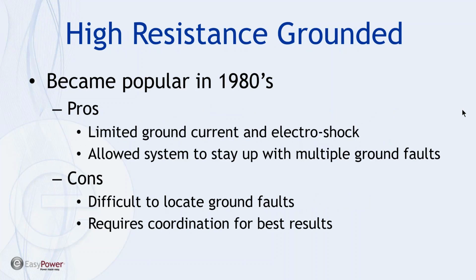And then in the 1980s, the system of high resistance grounding came into vogue, in part because it limited the amount of ground current and the electroshock potential in the system, and it allows the system to stay up with multiple grounds. The downside was, again, if we have the ability to tolerate multiple grounds, it wasn't always easy to locate each and every one, and for certain, it does require coordination for best results. So that's kind of where we stand today between the two options.